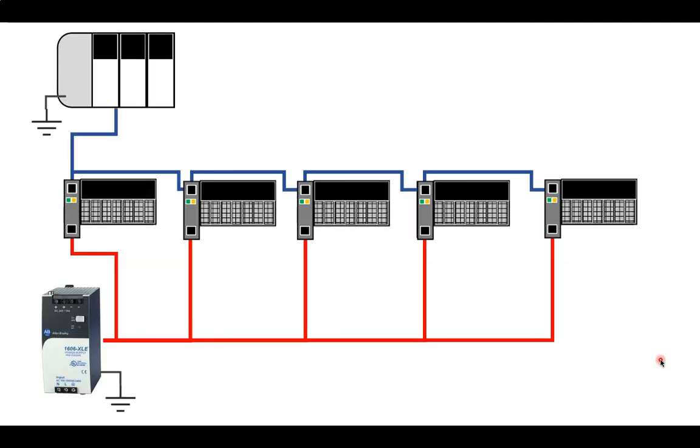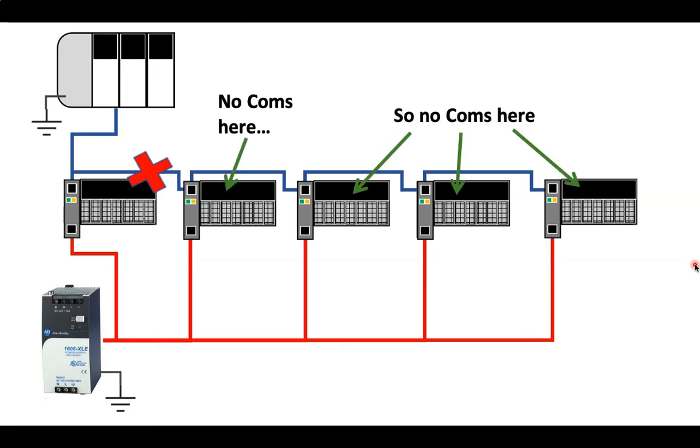Then number 3, you can look at the topology to see if other devices are also down in that network. If there is no redundancy, then multiple devices will be lost if one link is broken. You can also verify if the cable is not damaged, and you can also ping the devices to see if they are indeed on the network.